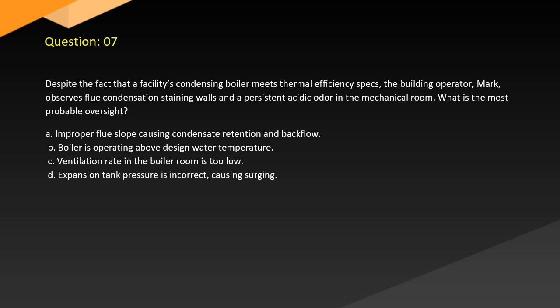Question 7. Despite the fact that a facility's condensing boiler meets thermal efficiency specs, the building operator, Mark, observes flue condensation staining walls and a persistent acidic odor in the mechanical room. What is the most probable oversight? A. Improper flue slope causing condensate retention and backflow. B. Boiler is operating above design water temperature. C. Ventilation rate in the boiler room is too low. D. Expansion tank pressure is incorrect, causing surging.